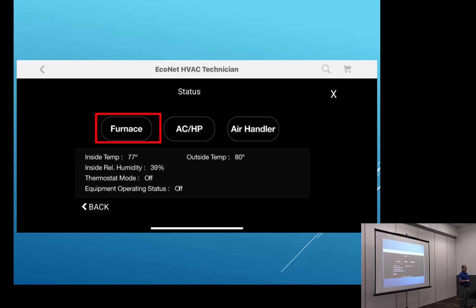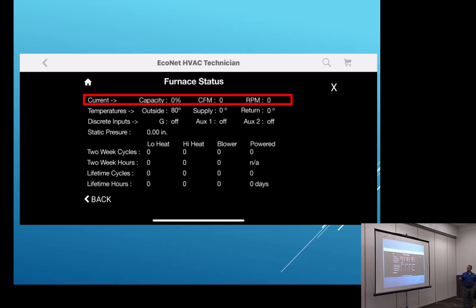Status. This is going to be a screen, if you call me, that we're going to become infinitely good at, okay? Because I'm going to want pictures of some information off of this screen to help me help you diagnose what's going on with the system, okay? So if we go for the furnace, in here it's got our furnace status screen. If we're working on a furnace, I want a picture of this screen so I can see what the static pressure is, our RPM, and our CFM.